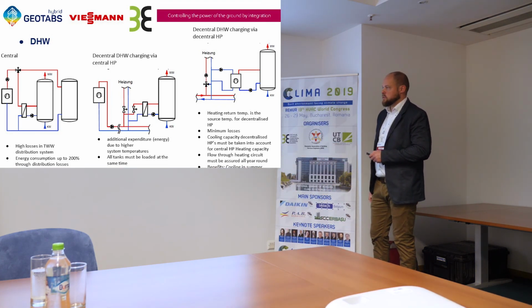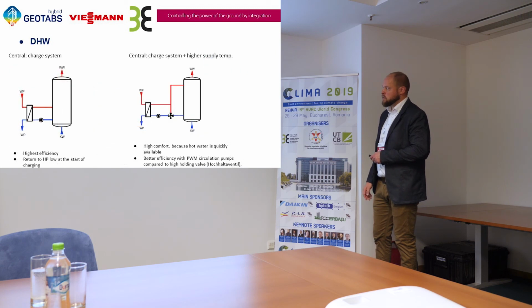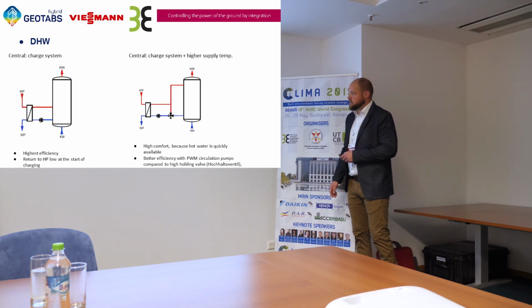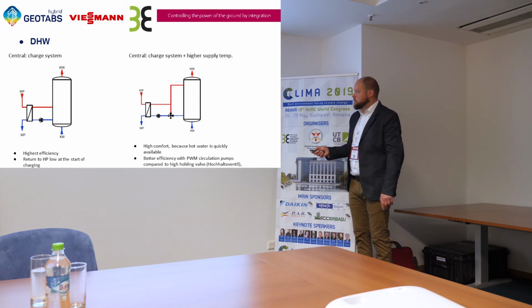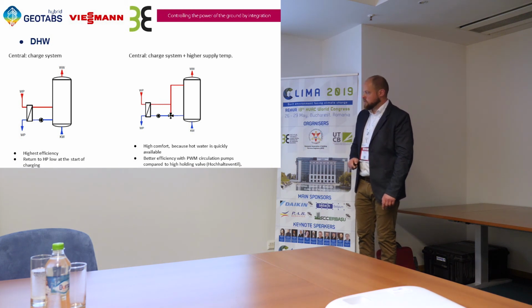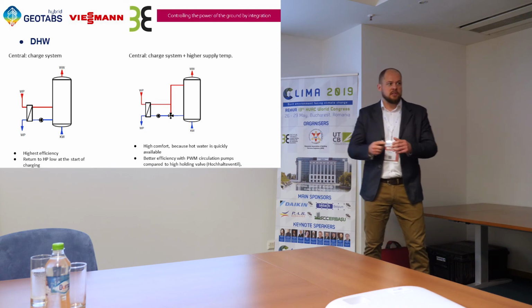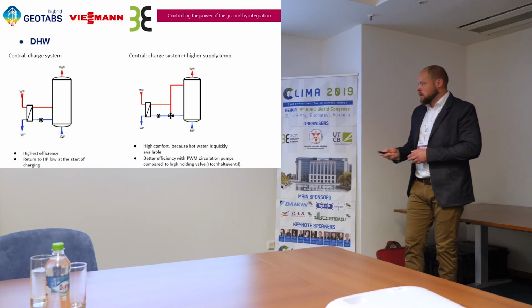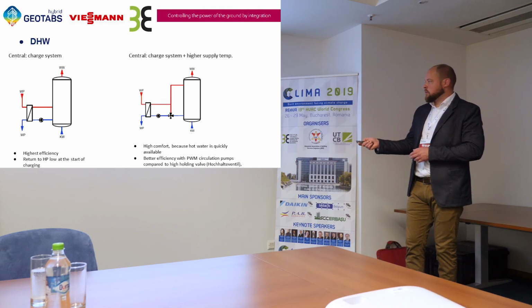There are some different system types. If you want to charge at higher temperatures, you can use this mixing valve to increase the temperature, the return temperature in this case, so that the departing temperature also will increase. So you can load the buffer tank a bit higher. This increases the comfort of the domestic hot water because hot water is quickly available. We also have another system without this valve, but then we use a PWM controlled circulation pump.